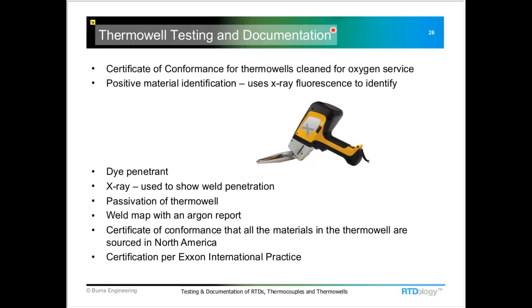We see this a lot of times on some of the more exotic materials where corrosion and having a failure due to corrosion would be a significant event. So regular X-rays can be used to show potential cracks within a thermowell, or to ensure that a weld has been made with 100% penetration.